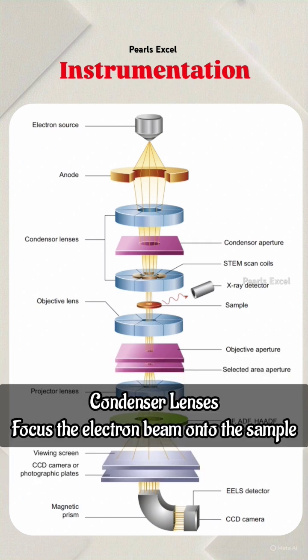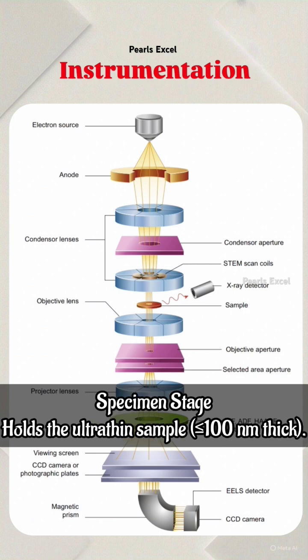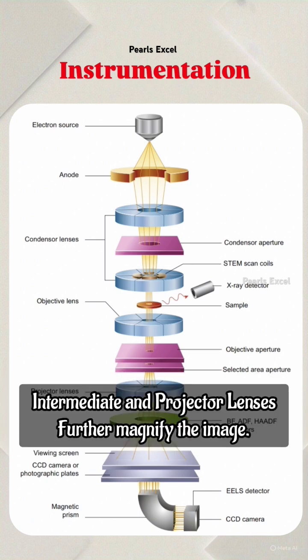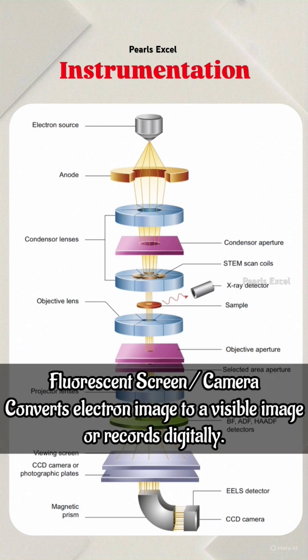Condenser lenses focus the electron beam onto the sample. The specimen stage holds the ultrathin sample, less than or equal to 100 nm thick. The objective lens and aperture form the initial magnified image; the objective aperture improves contrast. Intermediate and projector lenses further magnify the image. A fluorescent screen or camera converts the electron image to a visible image or records it digitally.